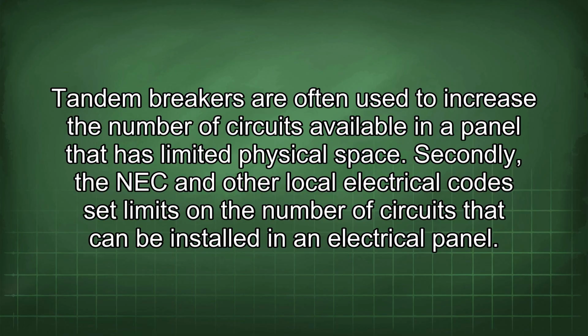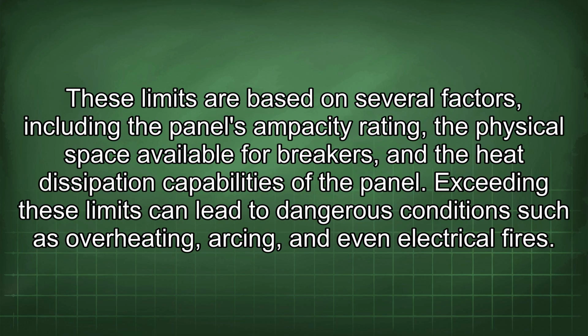limited physical space. Secondly, the NEC and other local electrical codes set limits on the number of circuits that can be installed in an electrical panel. These limits are based on several factors, including the panel's ampacity rating, the physical space available for breakers, and the heat dissipation capabilities of the panel. Exceeding these limits can lead to dangerous conditions such as overheating, arcing, and even electrical fires.